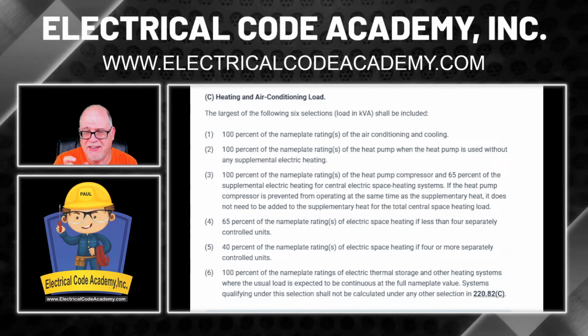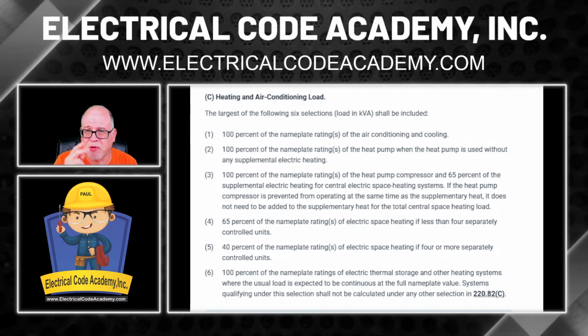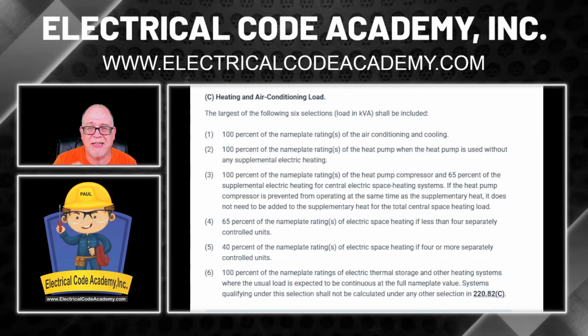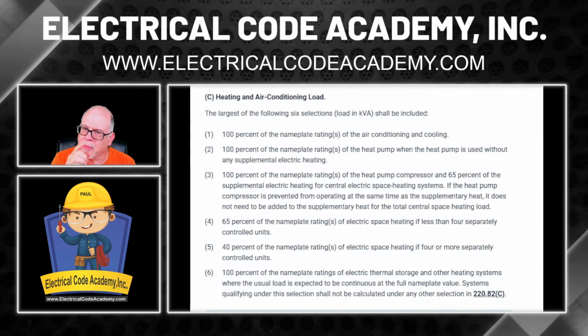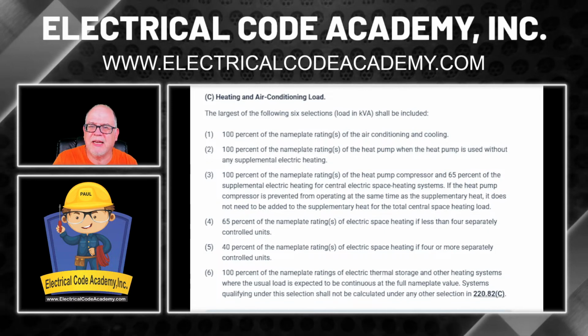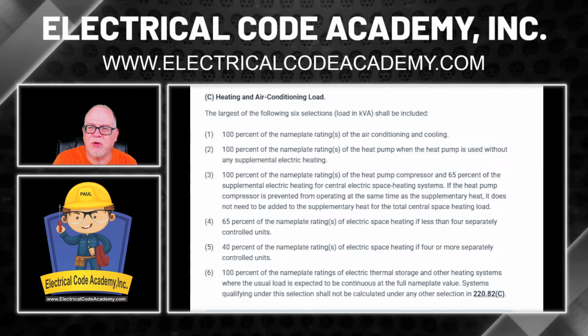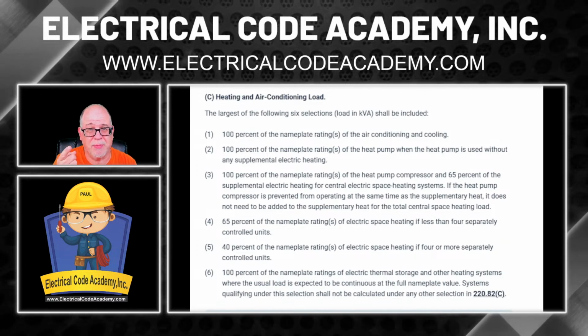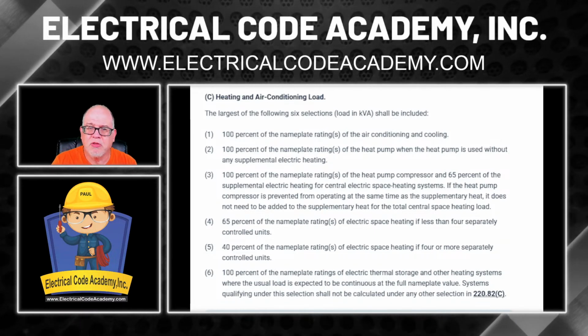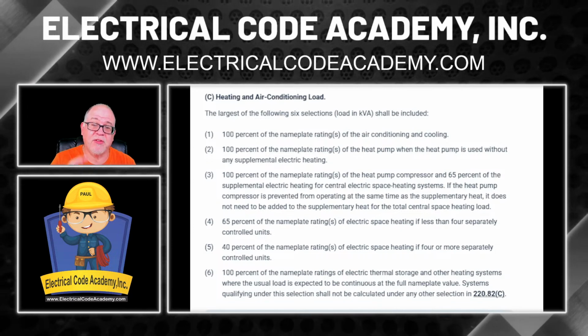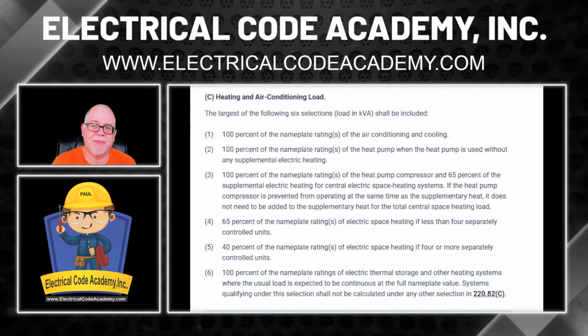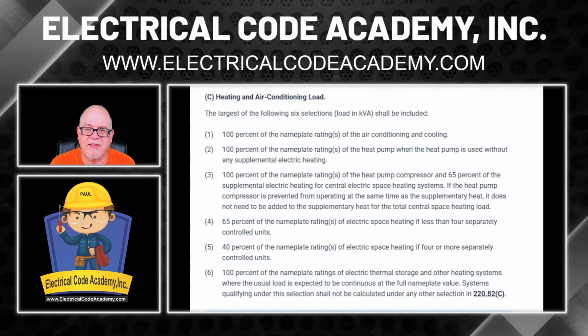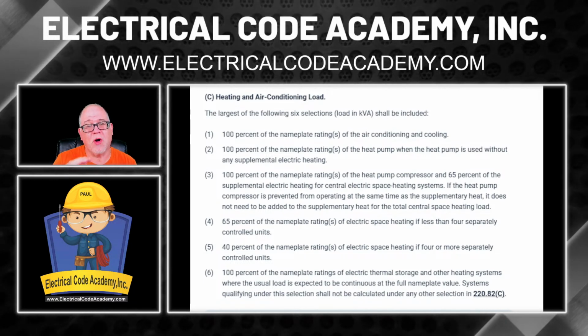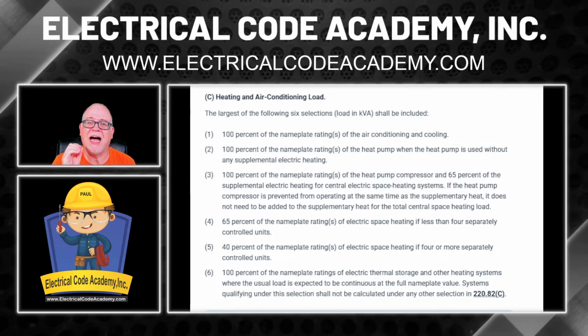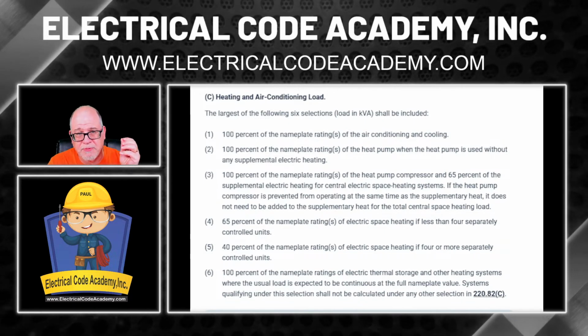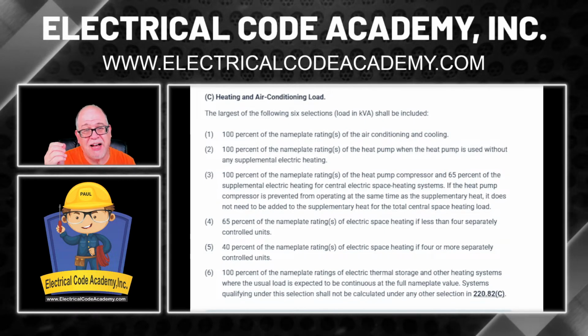Now we need to see that heat. Looking down the list here, number 2 is a heat pump. Number 3 is still talking about heat pumps. Number 4 is 65%, but that's electric space heating when you have less than 4. Well, we had 6, remember? So then we have number 5. Number 5 says 40% of the nameplate rating of electric space heating if there are 4 or more separately controlled units. Well, we had 6. So obviously we're going to be comparing number 1 for AC versus number 5 for the heat.